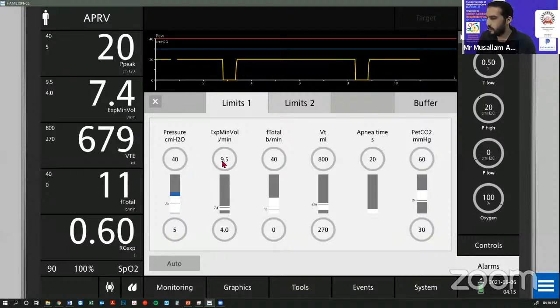For the minute ventilation, most textbooks mention 5% below and above the minute volume that you have. The frequency, 10 breaths above and below the one that you set, or the patient is breathing. Tidal volume, the same thing, they mention 10% above and 10% below. Or for me, I use like 100 or 75 ml above and 75 ml below. For the apnea time, if he is an adult, usually 20 seconds is the most appropriate alarm.